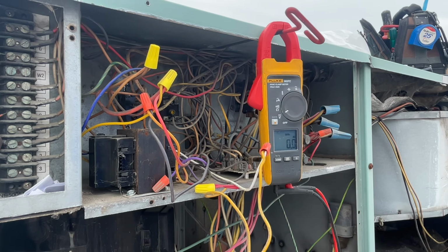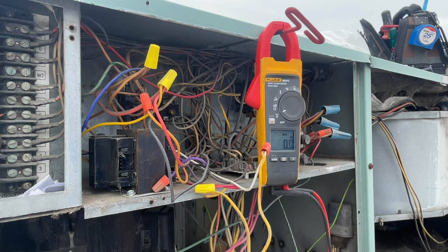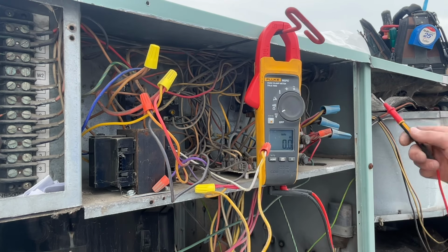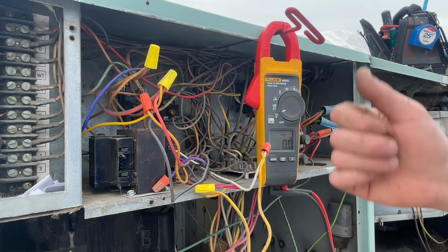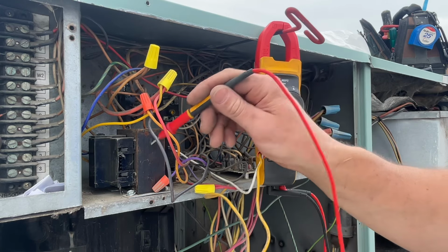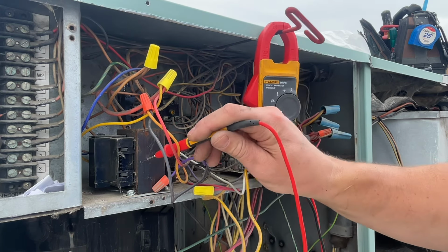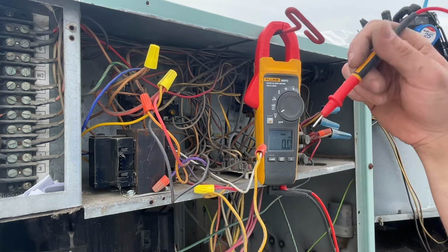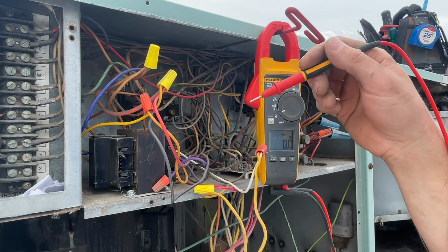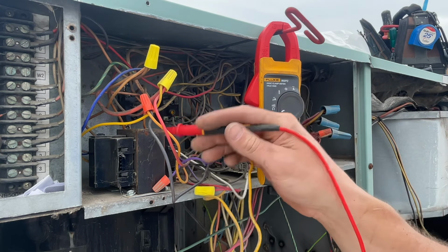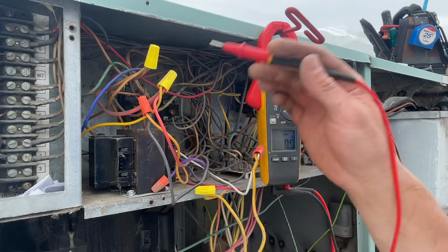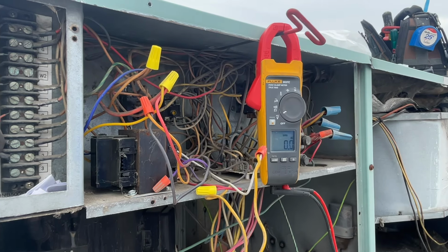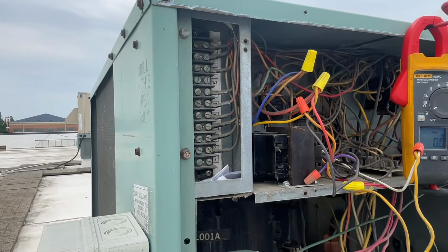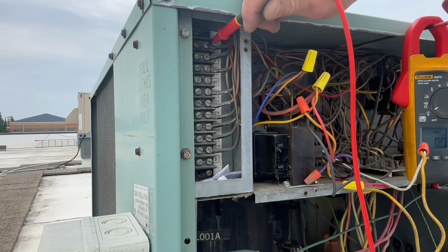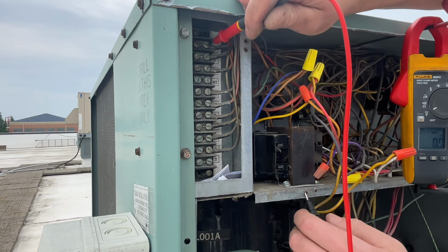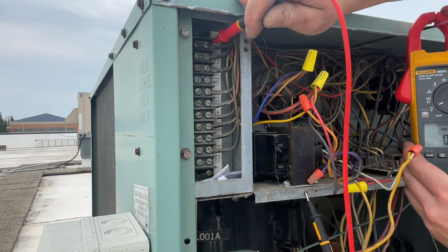Okay, so that big transformer has 2 purposes in this unit. One is to provide 208 volts for our blower fan, and second is for this control transformer here. They're trying to bring our 600 volts down to 208, 230, and then this transformer here takes our 208, 230 to 24 volts. So the 24 volts we don't have available right now because that big transformer is blown up, and I know that because I went across our R terminal to ground here, and we have nothing on our meter.